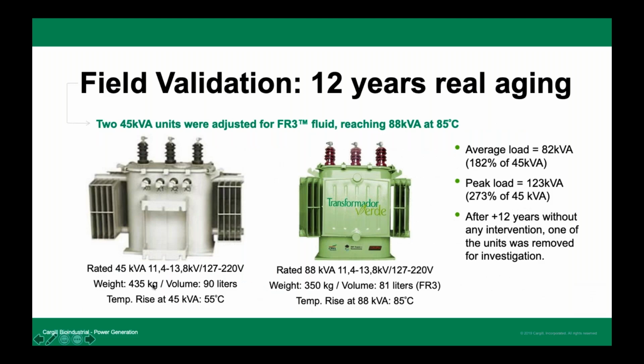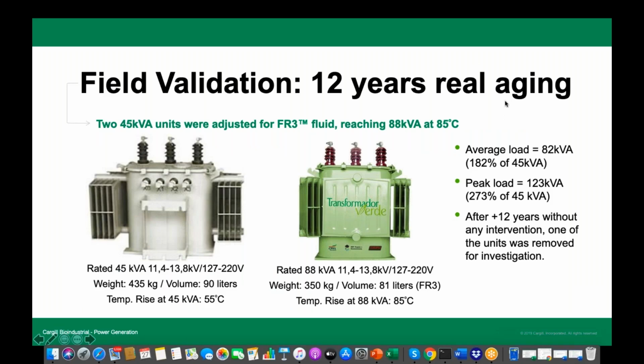What the utility decided was to take out this transformer, because it had been on the network for 12 plus years and their experience with mineral oil transformers was horrible. Some of the other conductors were also horrible. So after 12 plus years, they decided to remove this transformer, although it was working all fine, and see what happens inside. Just move to the next slide and you will find the results there. They dismantled the transformer. Next slide. They opened it, and inside, the transformer was as good as brand new. Next slide, please.